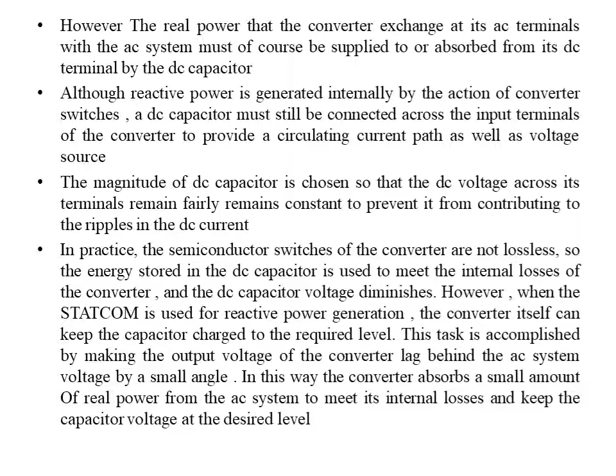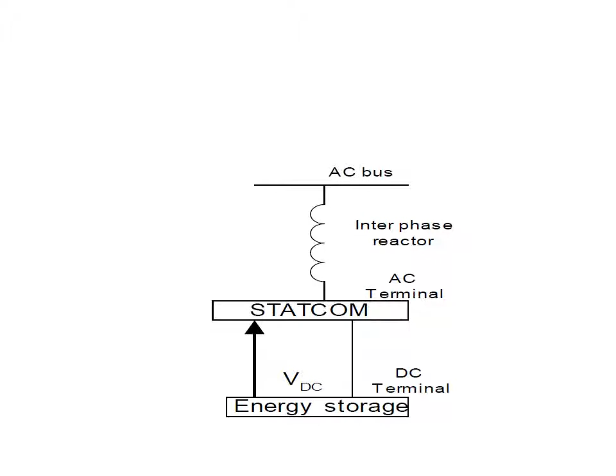So this is the system of a STATCOM connected to an AC bus with energy storage. The reactive and real power exchange between the STATCOM and the AC system can be controlled independently of each other. Any combination of real power generation or absorption with var generation or absorption is achievable if the STATCOM is equipped with an energy storage device of suitable capacity, as shown below.